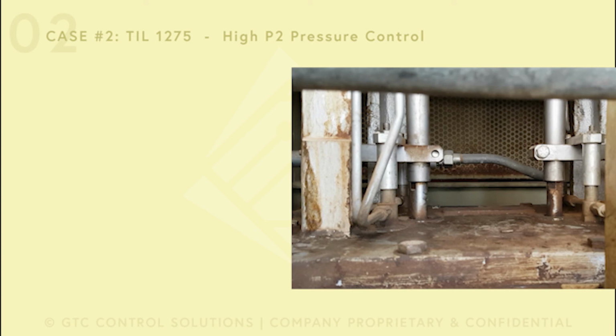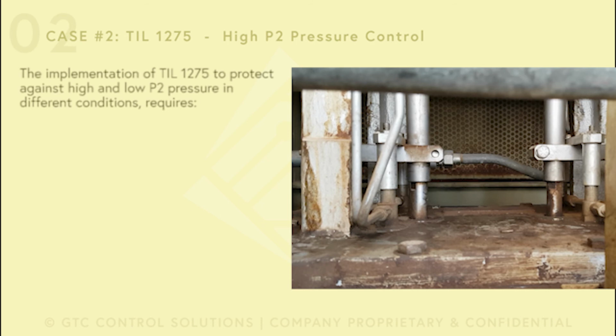What is P2 pressure? P2 pressure is the pressure between the first valve in the gas fuel module, the speed ratio valve, and the gas control valves. That cavity between these two valves holds P2 pressure. In order to have a safe start, the P2 pressure cannot be above 6 psi before the start. The speed ratio valve is not tight shut off. The valve is not designed to be tight shut off.